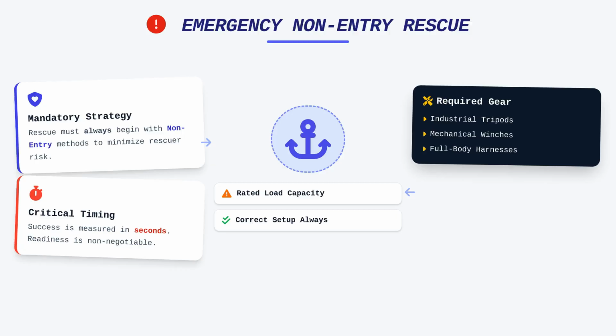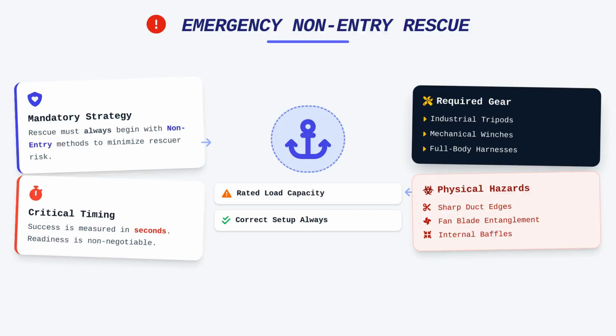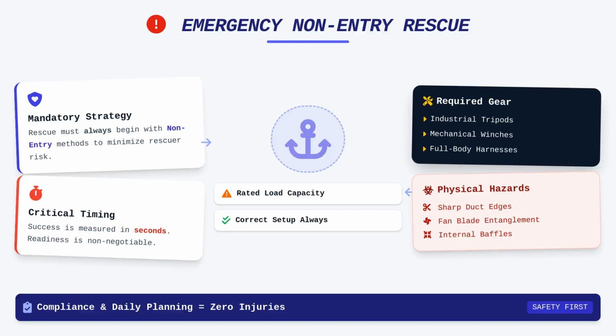Part of your overall project planning must include an assessment of potential physical hazards that might complicate a rescue, such as sharp duct edges, mechanical entanglement hazards from fan blades, or restricted movement due to internal baffles. Your emergency response team must be trained, briefed, and ready to act, as the difference between a successful rescue and a tragedy is often measured in seconds. Integrating these procedures into your daily job site planning minimizes the risk of injury and ensures that your workforce remains compliant with legal mandates.